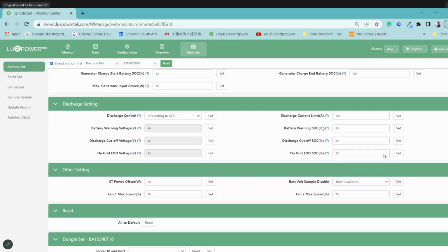And then the battery warnings SoC, that's based on what you want to set it to. Just be very cautious with this. If let's say you set it to 25% or 22%, your client's going to get notified and they might contact you because they don't understand. But you can just explain to them. So what I like to do is I just program it the same as the discharge cutoff.